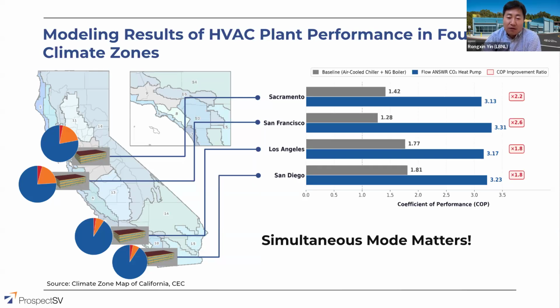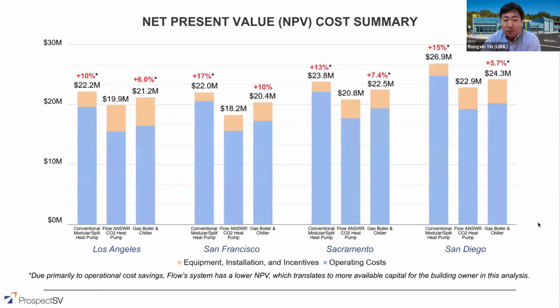That's why we have a huge improvement of COP in the Sacramento and San Francisco areas, because there are more operation hours for simultaneous heating and cooling. But in Southern California, Los Angeles and San Diego, which are cooling dominant, we have fewer hours of the combination mode of the heat pump unit. But still, during the winter season, if you run the unit in simultaneous heating and cooling mode, that drives high performance of the unit, with improved COP compared to the air cooled chiller plus natural gas boiler baseline. Which means simultaneous mode matters. That is the main driver I want to point out here. I think that's all. All right, Adam, back to you.